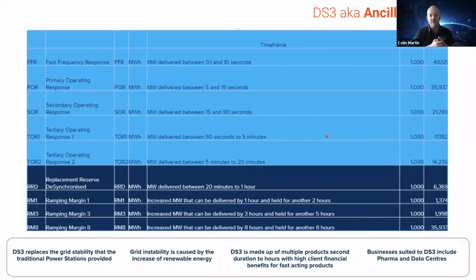The ancillary services are slightly different - these are the fast acting products, 0.1 seconds reaction time we're talking here. This is batteries and other really fast acting responses, acting autonomously with control signals going at the speed of light, picking up a slight deviation from 50 to 49.5 hertz on the grid, and the battery kicking in to bring that frequency back into the refined tolerance range.